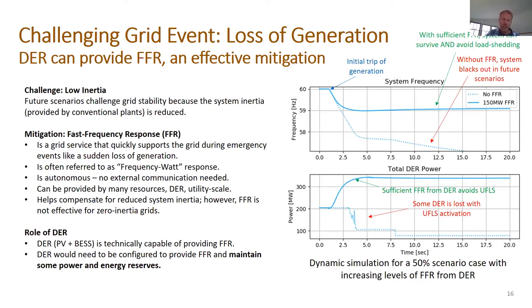This is a commercially available option now on modern DER. And it is capable of providing this as long as the DER is, I would say, pre-positioned to respond, to have some headroom, both in power and in energy, such that if there is an event, there is some capability in the DER across the grid to respond quickly and help stabilize the grid.